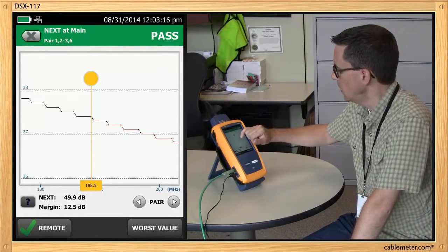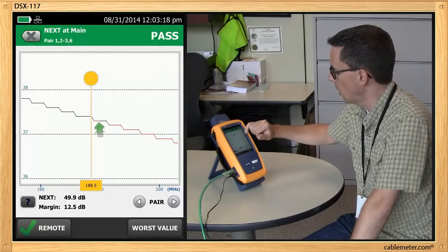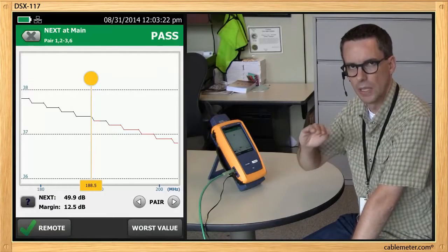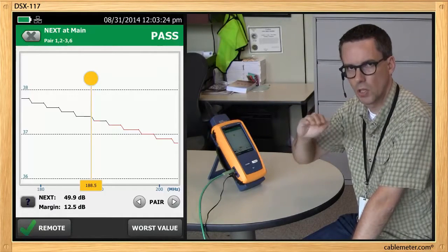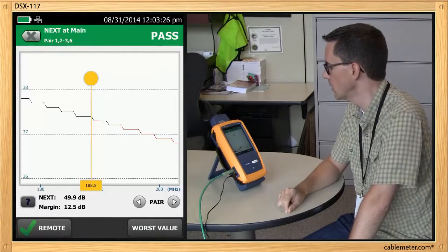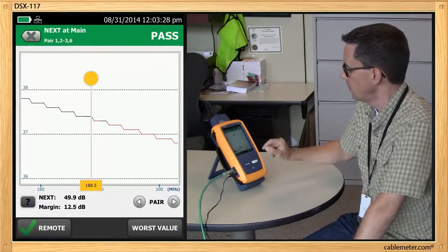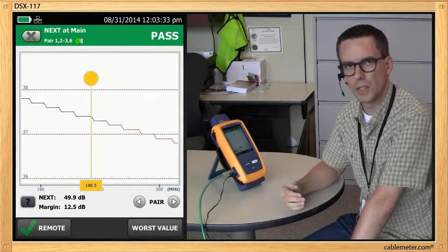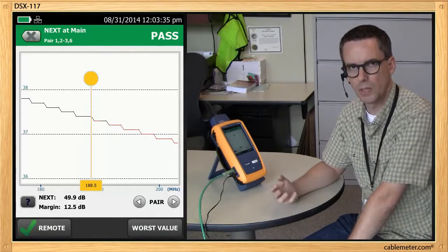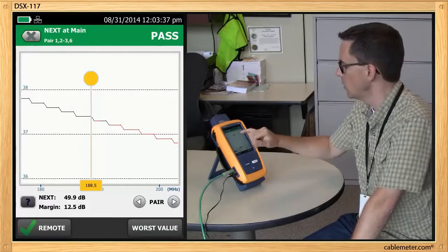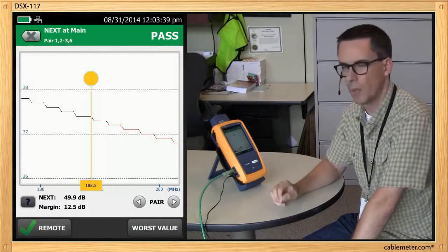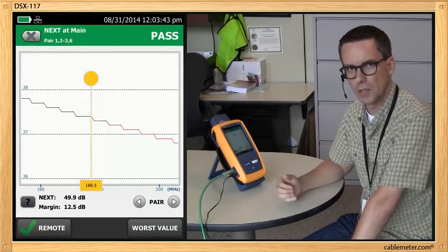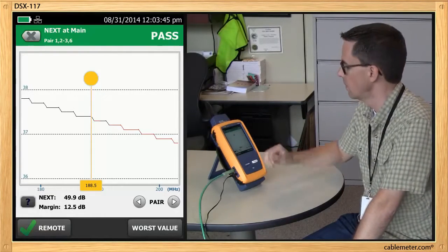Now you'll notice that a little bit after that it goes red and then black and then red again. And that's because of something called insertion loss deviation. It's not exactly smooth, the insertion loss, particularly when you're doing high frequency testing. So this is for crosstalk on 1236, and I said the 4 dB rule applies based on the insertion loss. Well, does it apply on the insertion loss of pair 12 or pair 36? It's pair 36. That's how it's defined in the standards.